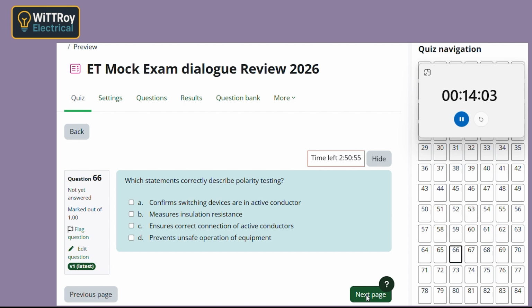Exactly. It looks off, but parts of the circuit can still be energized, which is dangerous. So polarity testing makes sure switching happens on the active. Yes, and that helps make the circuit safe to use. It's not about resistance or insulation, it's about correct connections.